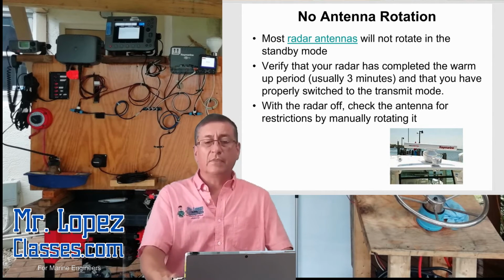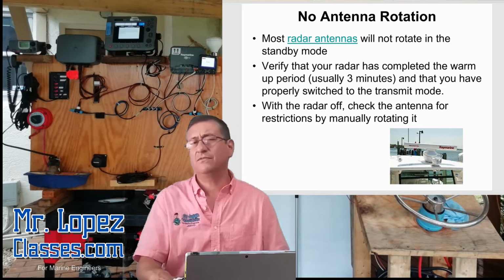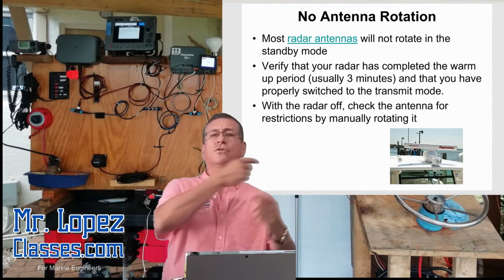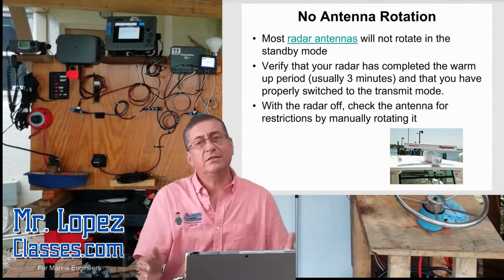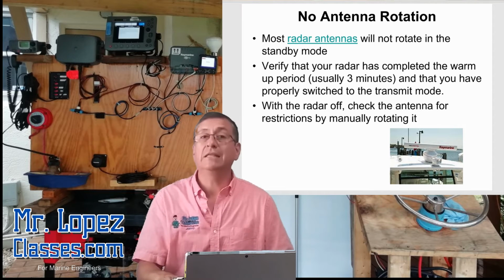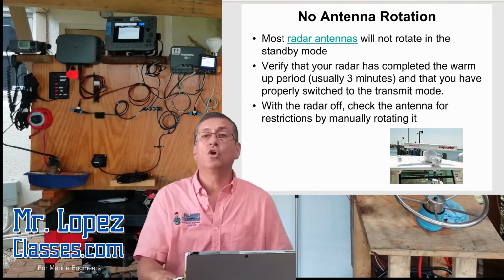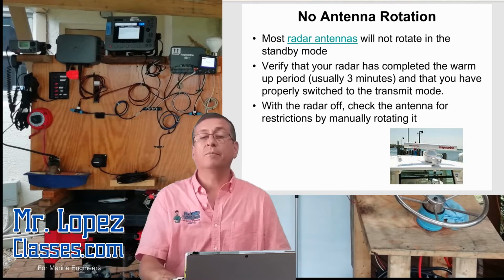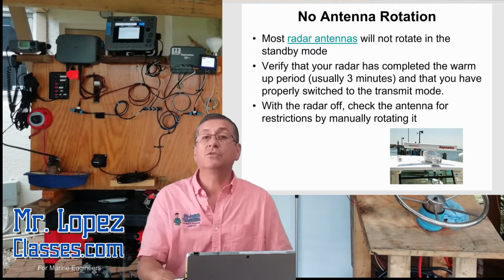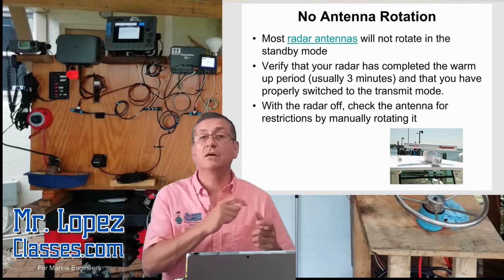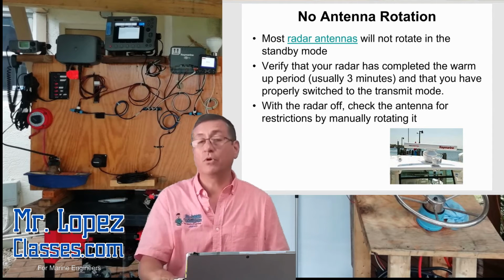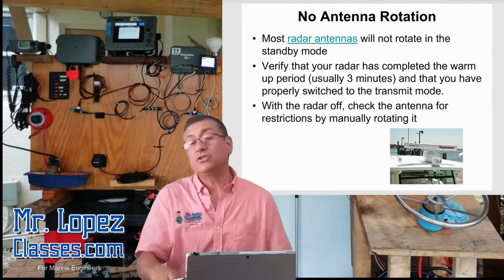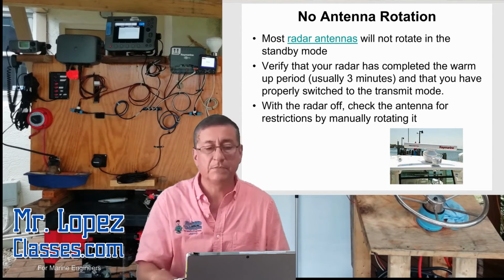All right, and no rotation. It is very common that the sensor is not rotating. This is normally because the belts internally are broken, or because the ground is disconnected, or because the mechanism is broken. One of the gears internally in the mechanism is broken. It's not common, but it happens.